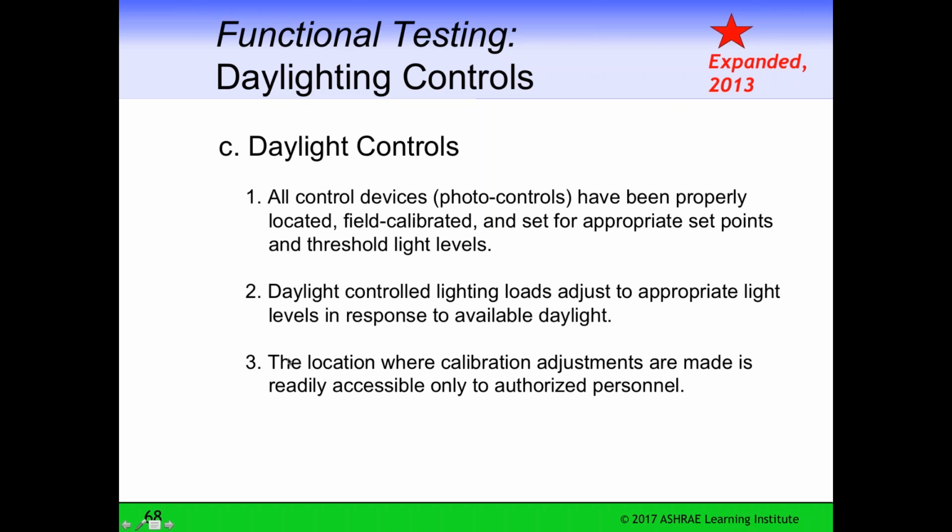One of the early daylighting systems that I worked on, in a building in Minnesota, this type of testing was not done. There was a very good design, but the installation was really screwed up and the system didn't work. It wasn't calibrated, with the wrong number of devices in the wrong location, and 0% savings from the daylighting.